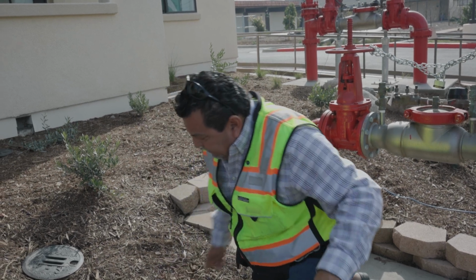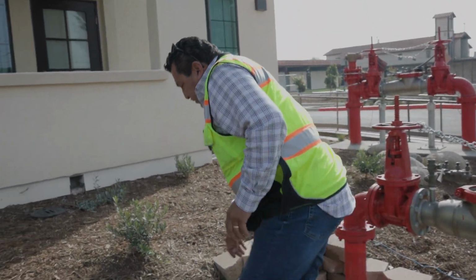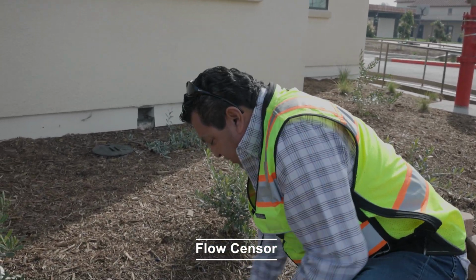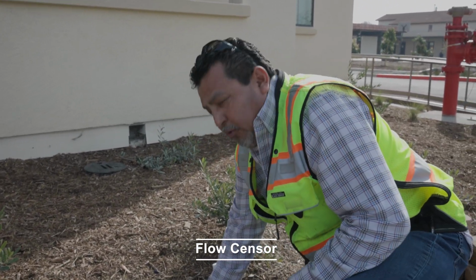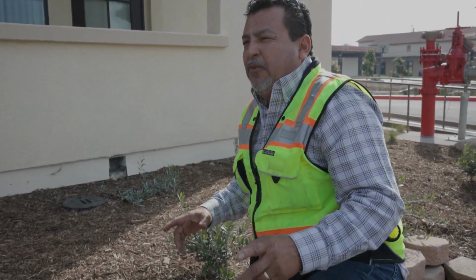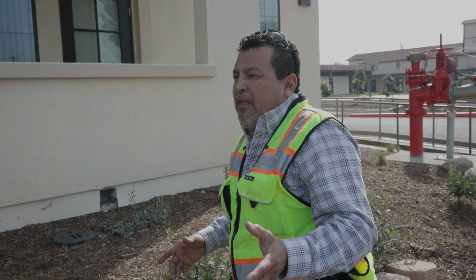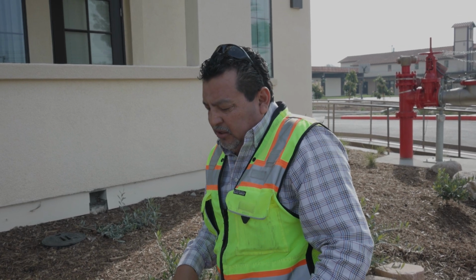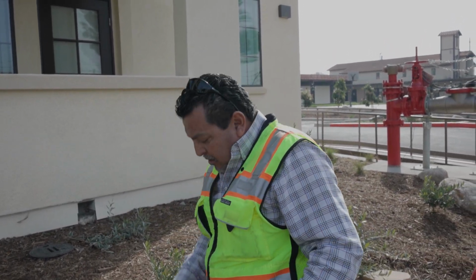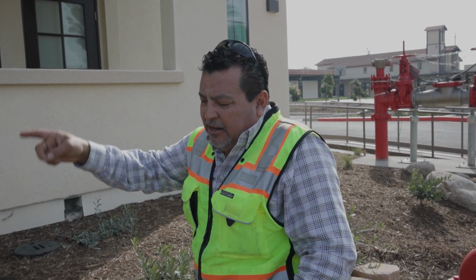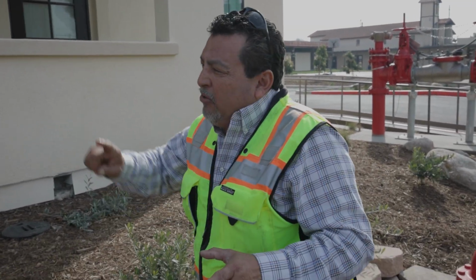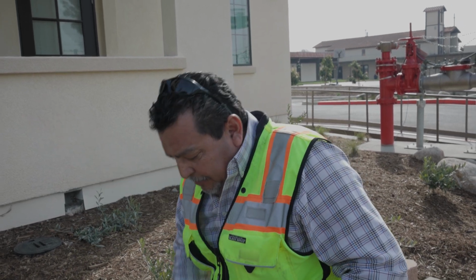Then we have the flow sensor here. What this does is read the flow through the system, in gallons per hour or gallons per minute. You need about 30 gallons per hour, and this is gonna be the one reading the flow. If there's a broken line, it's gonna shut the system off, so there's no water running through the system. It sends a signal to the controller telling it to shut off because we have a leak. If your valve is sitting at like 45 psi and it reads more than that, that means there's a leak or a broken line, and you gotta go back to the controller, read the flow, and fix the problem.